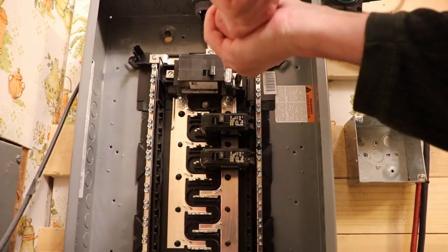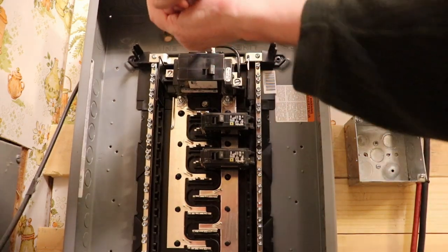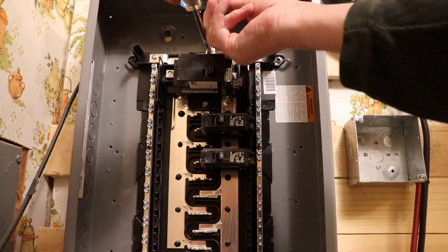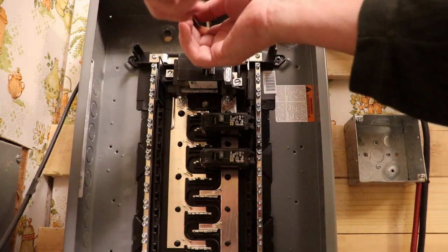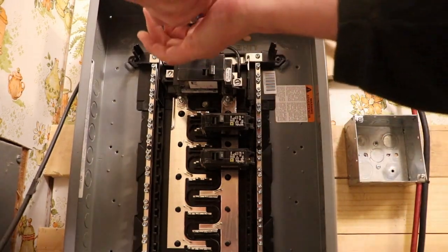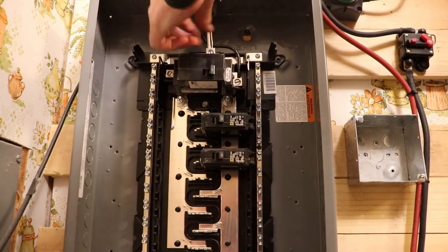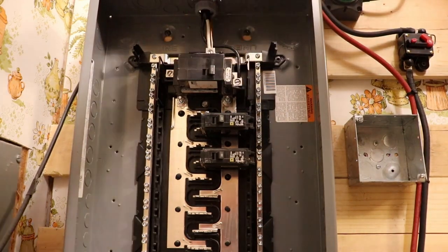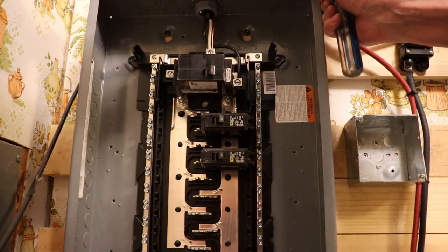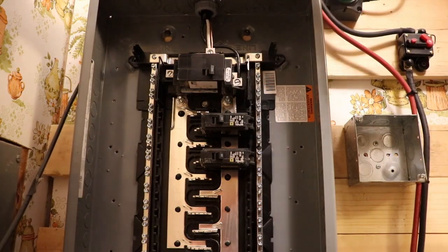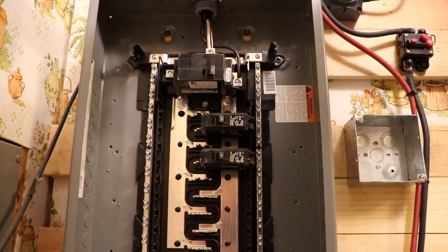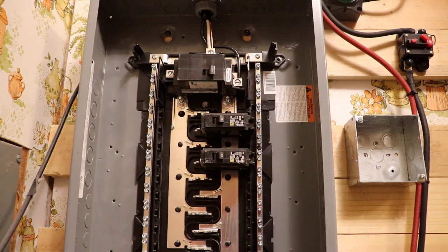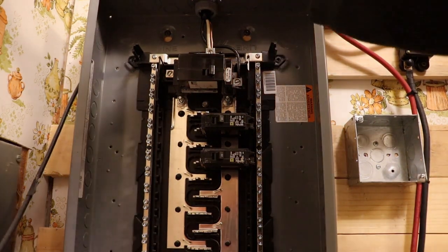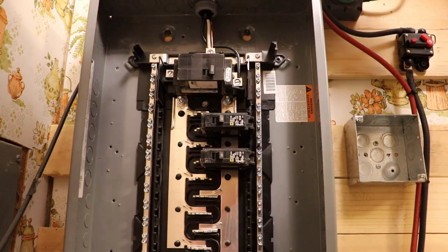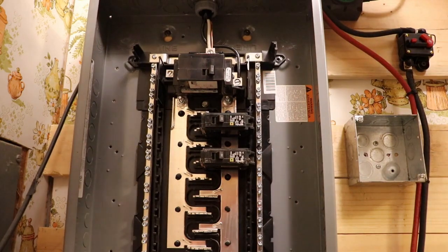I want to make sure they're good and tight and snug. Don't worry if the wires extend beyond this lug - it's made that way for a reason, so you can see you actually got a good connection. Okay, those are good. Our next step is to get this tightened up. Don't tighten it too tight that you start crimping the wire itself on the insulation, because you can break through it, and that's not a good thing, since it can cause a short.